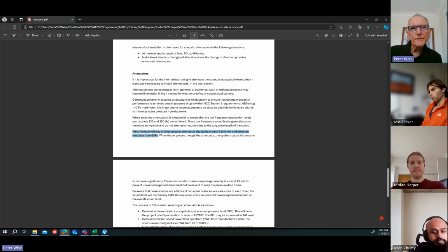Because what happens inside a rectangular attenuator is, because you have splitters, the air is accelerated. The velocity increases through the attenuator. So a good rule of thumb is to keep that around 5 to 6 metres a second, and usually the pressure drop will fall within that 40 pascals. That's not to say it always happens, you just need to check each one, but when you're doing your initial design, that's a good guideline.